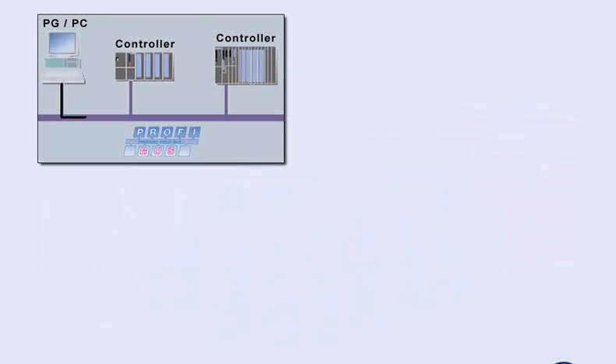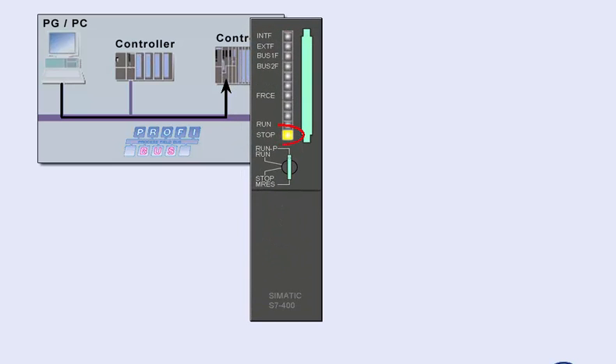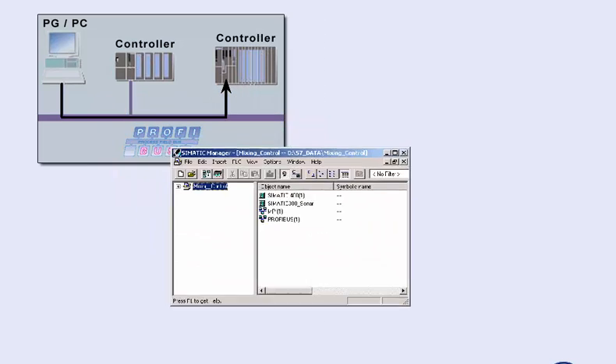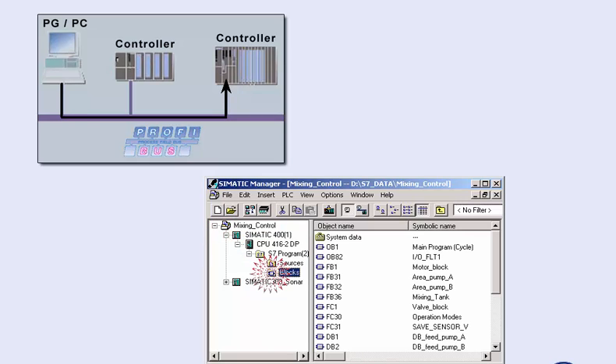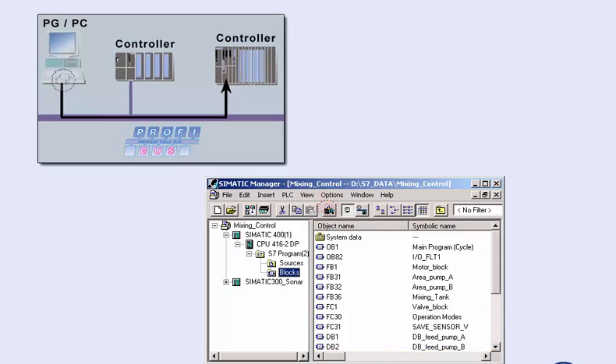This requires the programming device to be online and the CPU to be in stop mode. We open the offline project, which is located on the hard disk of the programming device, and select the station as well as the block container. The block container contains all runnable blocks of the user program. Pressing the download to target system button, we now transmit all blocks into the user memory of the CPU.